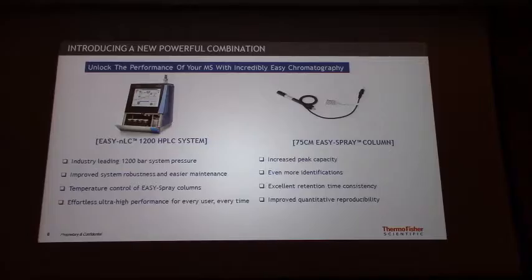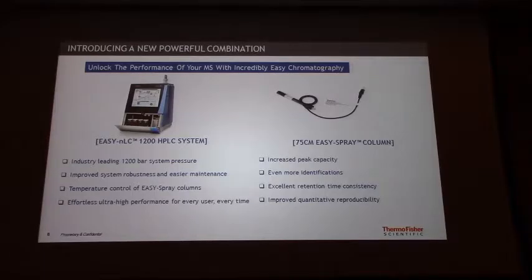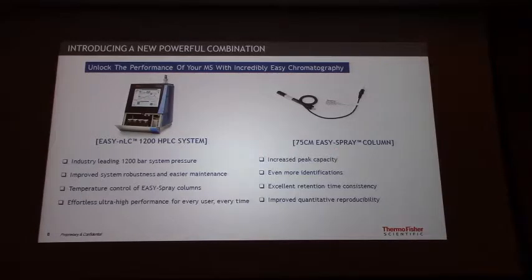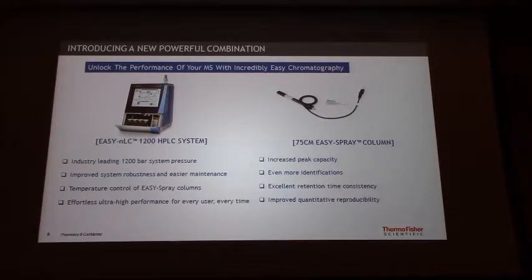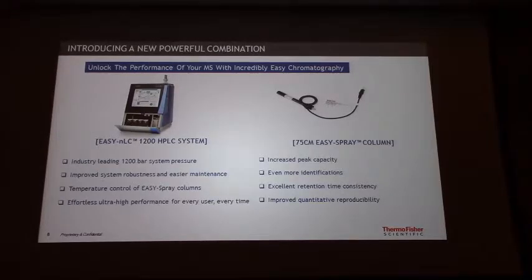The key for being successful in this workflow is the EasyNLC-1200, which is a very small, compact LC that allows for high pressure up to 1200 bar. We introduced it last year at HUPO. And what we are introducing this year is a 75-centimeter Easy-Spray column that allows very high peak capacity, very reproducible retention time, and even more identifications. It's a 75-centimeter, 75-micron ID column — it fits right in your machine, it's plug-and-play, and I think there is nothing in the market that allows for such capability.